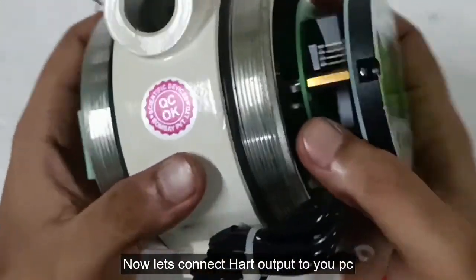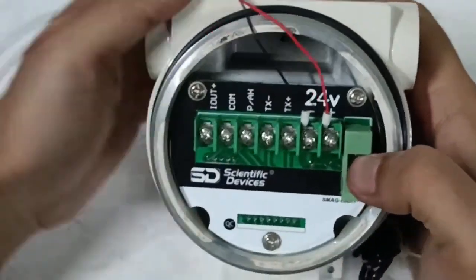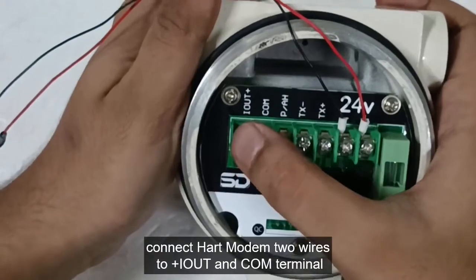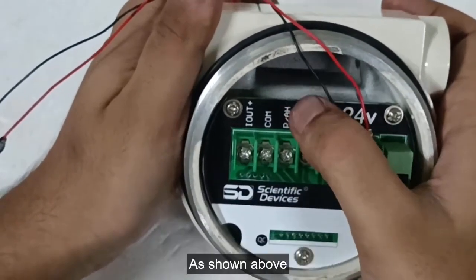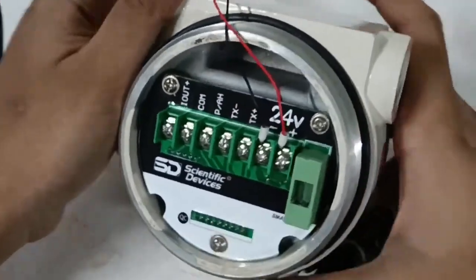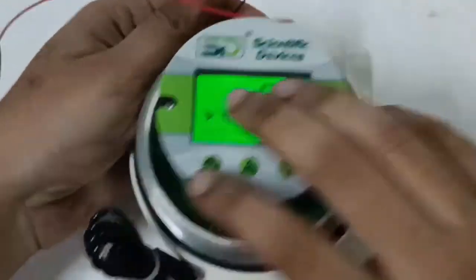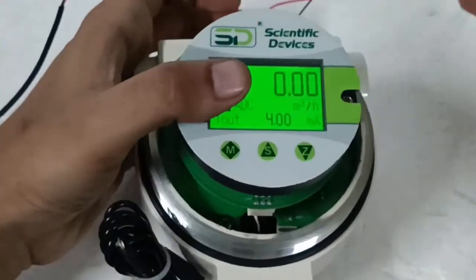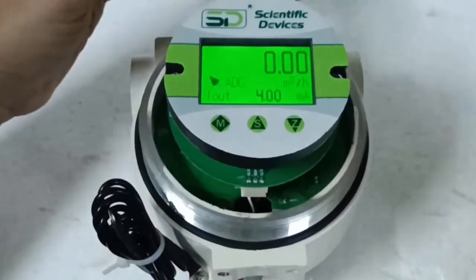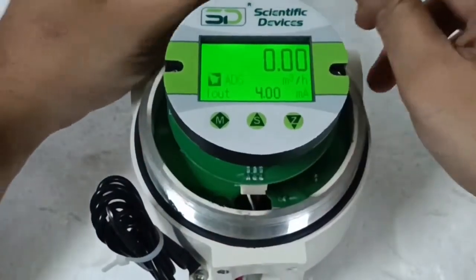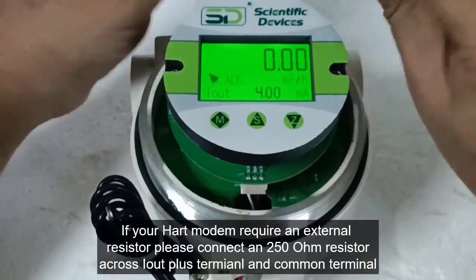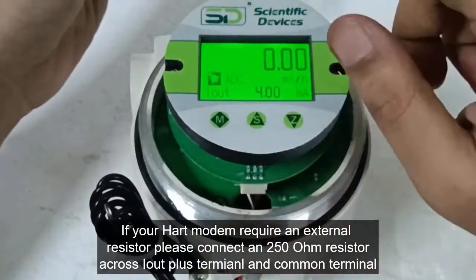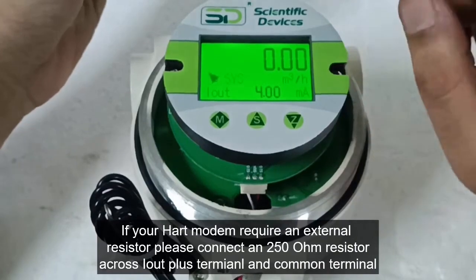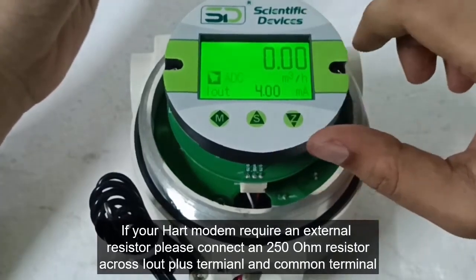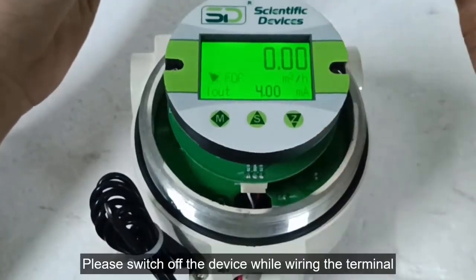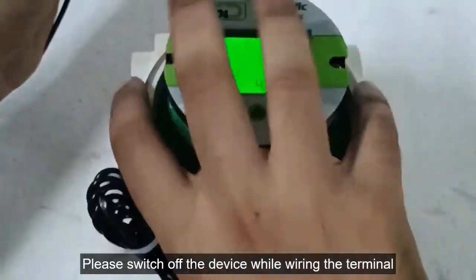Now let's connect HART output to your PC. Connect HART modem 2 wires to IOUT and COM terminal, as shown above. If your HART modem requires an external resistor, please connect a 250 ohm resistor across IOUT plus terminal and common terminal. Please switch off the device while wiring the terminal.